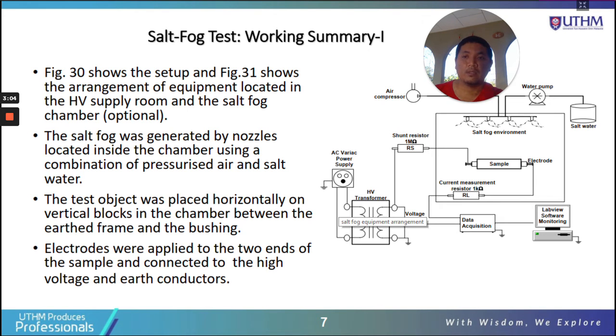Right, let's look at the description or the details of the salt fog test. As I said, salt fog was generated by nozzles located inside the chamber. We have salt water that is being pumped with an air compressor to spray it, to make that salt water become fog. And you can see here the test object placed horizontally on vertical blocks in the chamber between the earth frame and the bushing. The earth frame is connected to the earth, and the bushing is connected to the HV supply. So basically we have two electrodes applied to the two ends of the sample, one connected to the high voltage, one connected to the ground.